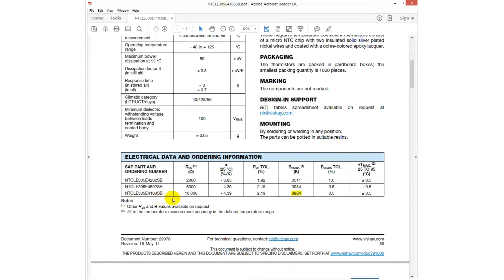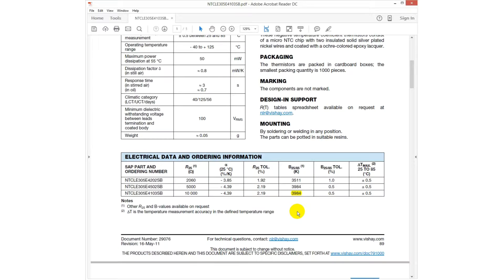The sensor for our object has a beta value of 3984K, which does not comply with the default settings of the controller.